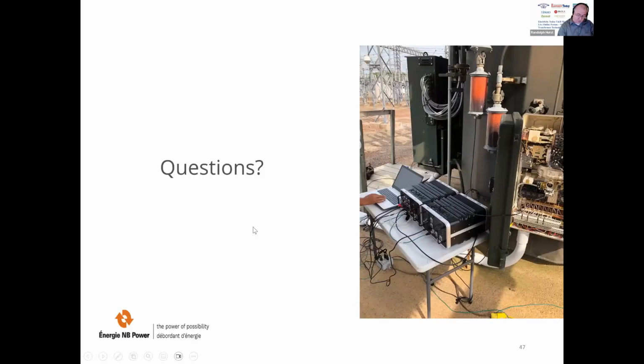I have a few questions here. You mentioned that 40 to 50% of transformer failures are caused by tap changer failures. Why is this? And what kind of mechanical failures cause this high rate? Well, in fact, it's a study, as I said in the second slide. The study has been done by CIGRE, Hydro-Quebec, and it's mechanical problems. I suspect personally it's because the tap changer is a complex mechanism. As soon as you have something complex, of course, it's more sensitive to problems. So the design of the tap changers is complex.